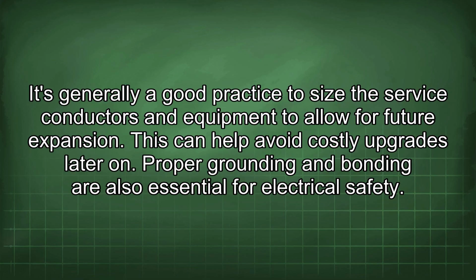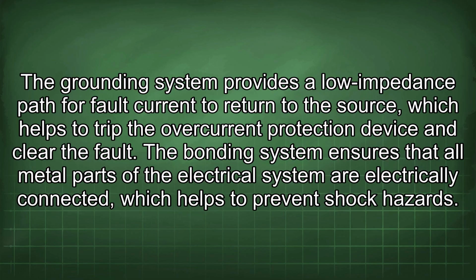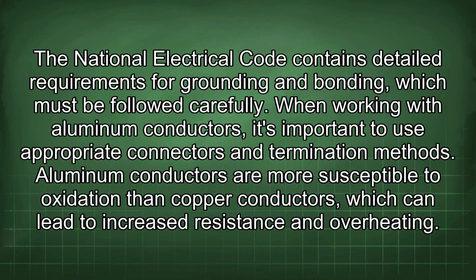Proper grounding and bonding are also essential for electrical safety. The grounding system provides a low impedance path for fault current to return to the source, which helps to trip the overcurrent protection device and clear the fault. The bonding system ensures that all metal parts of the electrical system are electrically connected, which helps to prevent shock hazards. The National Electrical Code contains detailed requirements for grounding and bonding, which must be followed carefully.